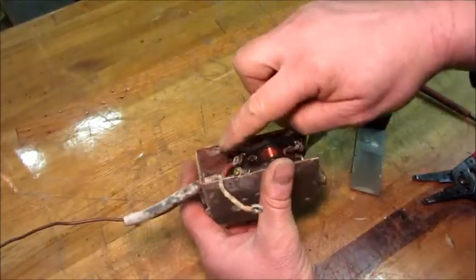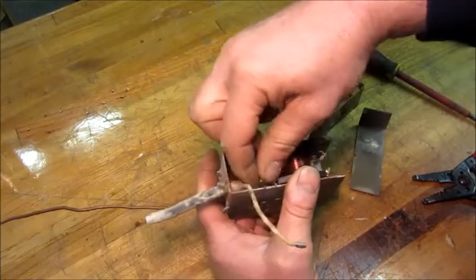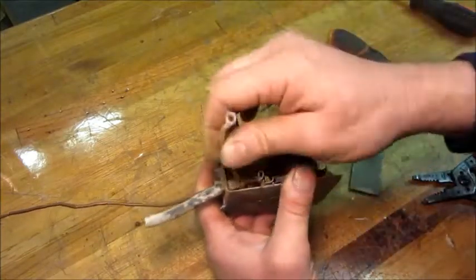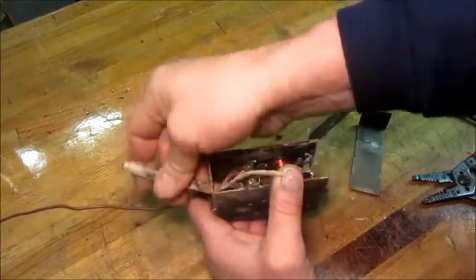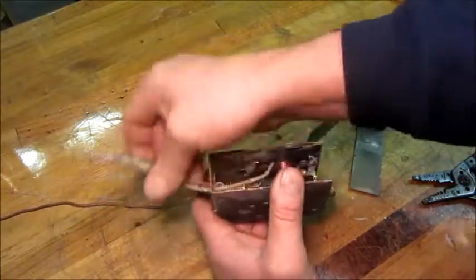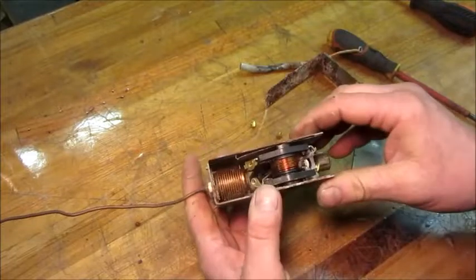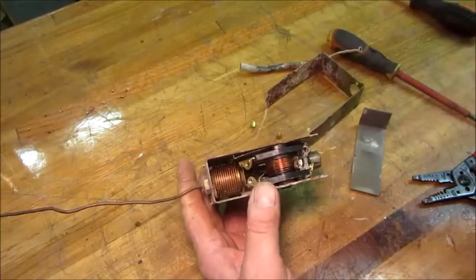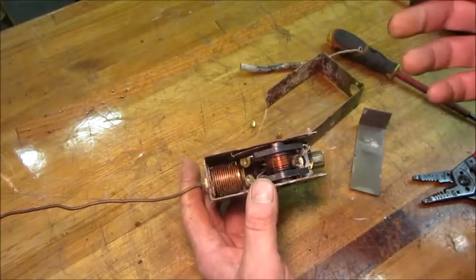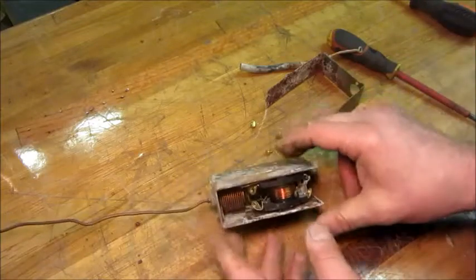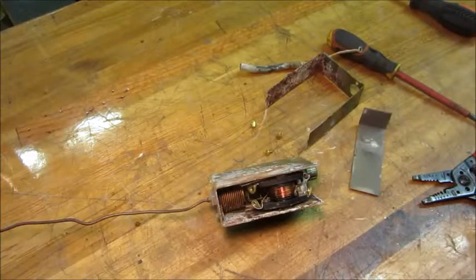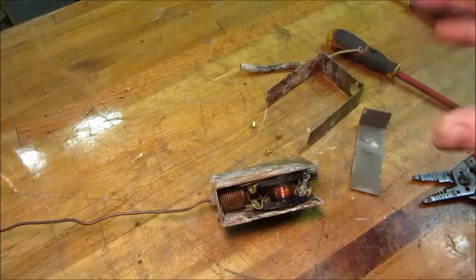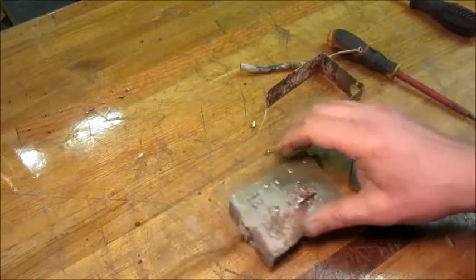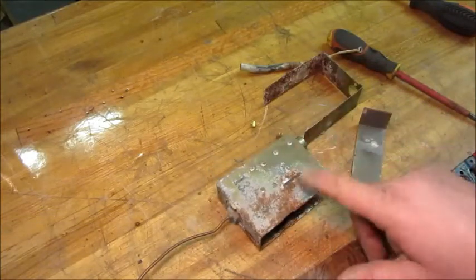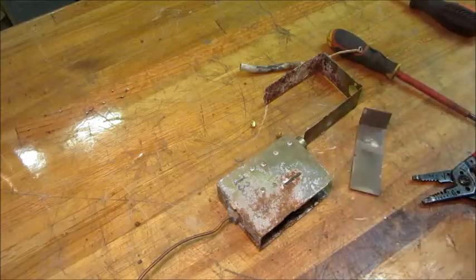And you notice how this is rusted on the inside. That happens due to moisture. The reason moisture builds up in there is because people have allowed the fridge to be operating in cold, and they've shut it off and left the door closed on the fridge cabinet. So that moisture stayed trapped in there without it being refrigerated anymore. So it was just free humidity. It got up in the insulation and did that to the start relay. So rebuilding this and rewiring it is probably all that was wrong with this ever.